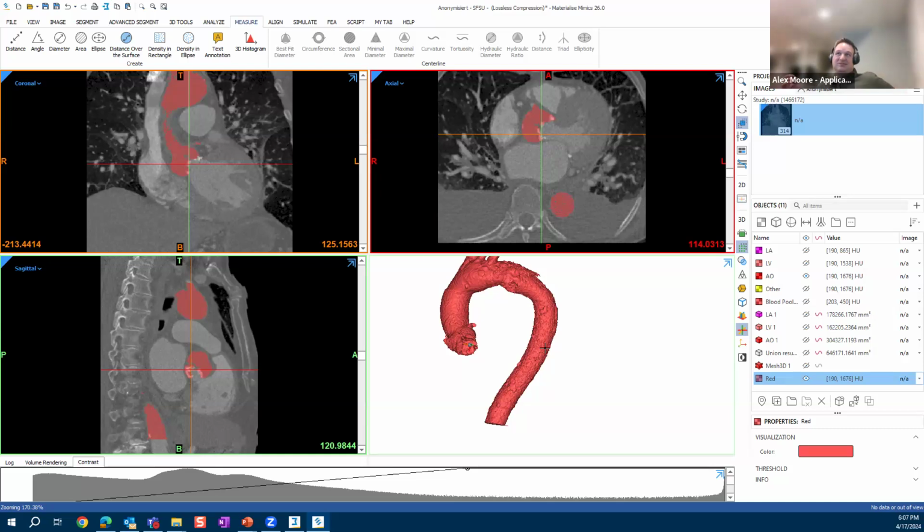But for the hospital itself, a lot of people will say it's practice of medicine. I think that's going to change at some point, where the FDA treats a lot of these point of care 3D printing labs as medical device manufacturers, where they have to have their own quality management system in-house and be audited and so on. On our end, we've gone through the clearance process to help them out. But it's a lot of work on their end as well to make sure that what they're creating and using for clinical use is safe and effective.